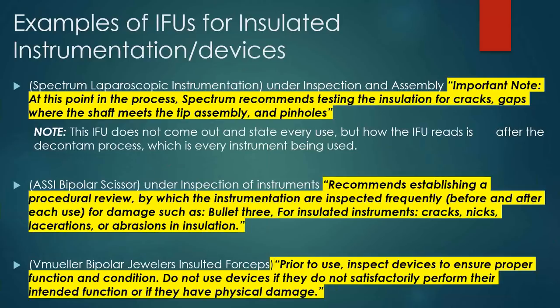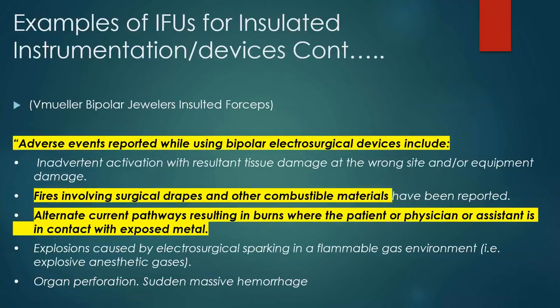Now moving on, there's some more examples of IFUs, but I want to expand on the V. Mueller bipolar jeweler forceps, because as I was reading down I found a section saying adverse events reported while using bipolar electrosurgical devices include, on the second and third bullets, fires involving surgical drapes and other combustible materials. This was actually one of the first IFUs I ran across that actually noted this. It also went on to say alternate current pathways resulting in burns where the patient, physician, or assistant is in contact with exposed metal.